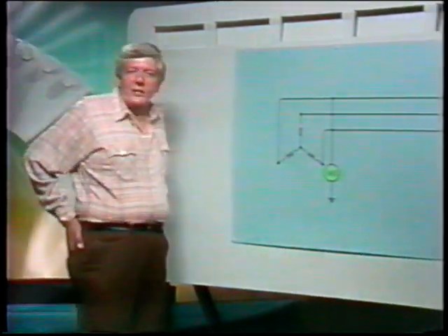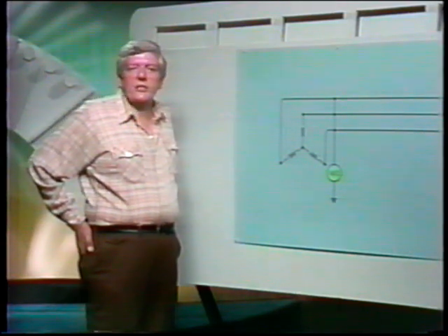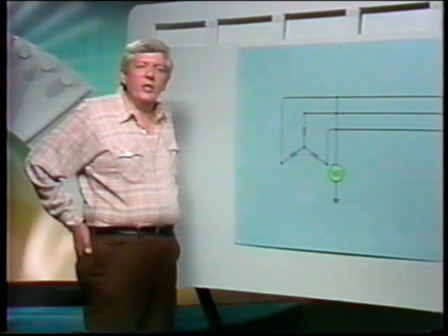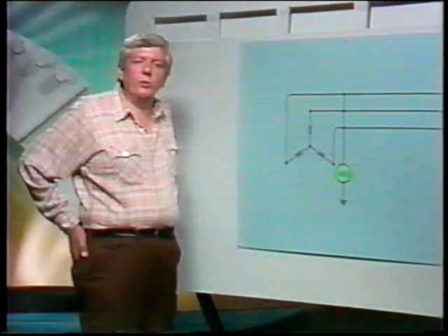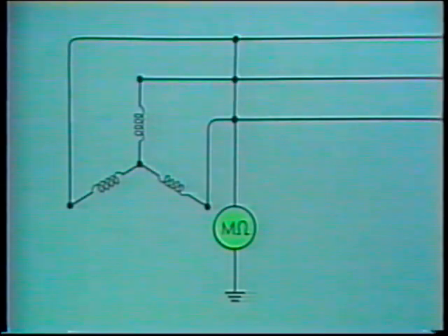We use a megohmmeter to measure insulation resistance. The megohmmeter indicates resistance in millions of ohms. Megometer readings are usually taken during overhaul in order to evaluate the condition of the generator's insulation. This diagram shows how the megohmmeter is connected to the generator windings.